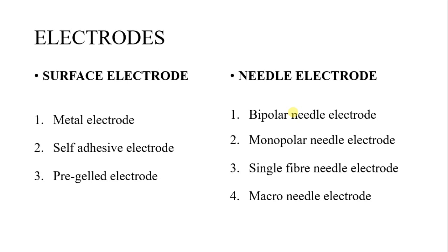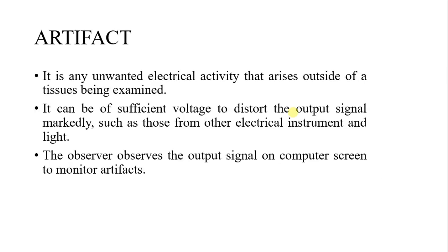Artifacts are any unwanted electrical activity that arises outside of the tissue being examined. They can be sufficiently high in voltage to distort the output signal, coming from sources such as other electrical instruments and lighting. The observer monitors the output signal on a computer screen to identify artifacts during the data collection process.